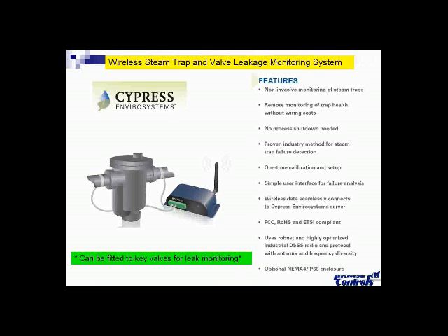You actually can track the data to see if a valve's leak is getting worse. You might start to see a leak and you go, well, it's not bad yet, we'll just monitor this. And maybe 8 months later you notice that the temperature seems to be going up on the downstream side. So you're starting to see that the valve's leaking more, and for the next outage you would schedule some maintenance on that valve.